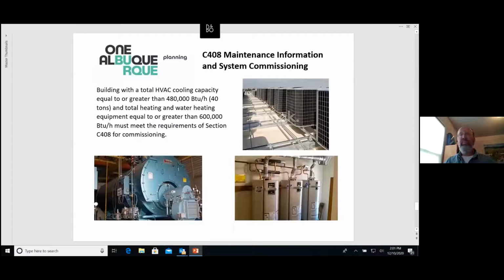I told you we'd talk about maintenance information and system commissioning. Larger systems, AC equal to or greater than 40 tons, 480,000 BTUs, and total heating and water heating equipment equal to or greater than 600,000 BTUs, will need to be commissioned, and Section 408 tells you all about the commissioning, what's required, and what that looks like.